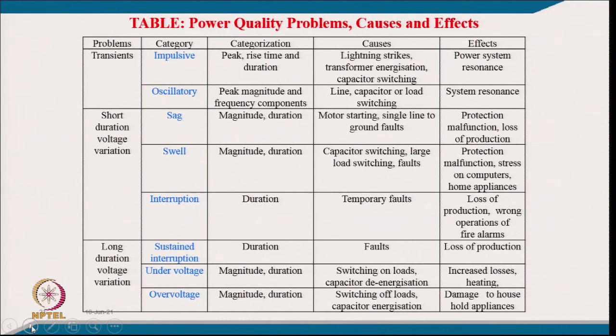Short-duration voltage variations include sag, swell, and interruption, quantified by magnitude and duration. Sag can be caused by large motor starting or single-phase line-to-ground faults, and affects protection system function. Swell results from capacitor switching or large load switching off, and stresses computers and home appliances. Interruption — common in India — may be due to temporary fault and causes loss of production and wrong operation of fire alarms.